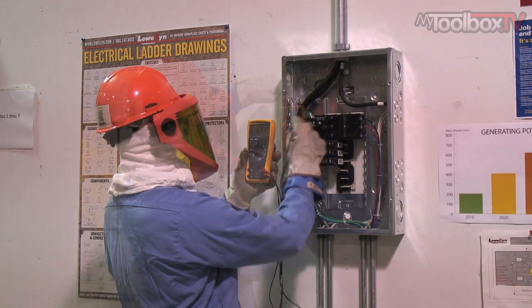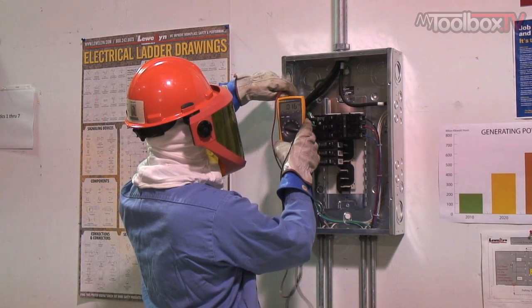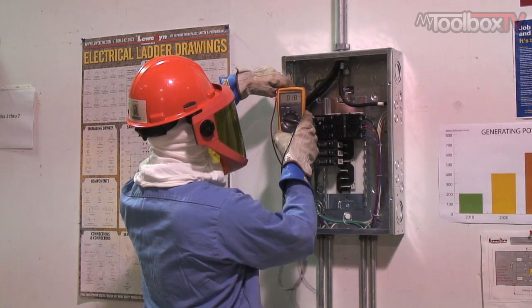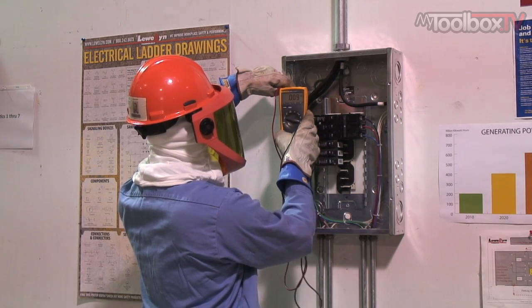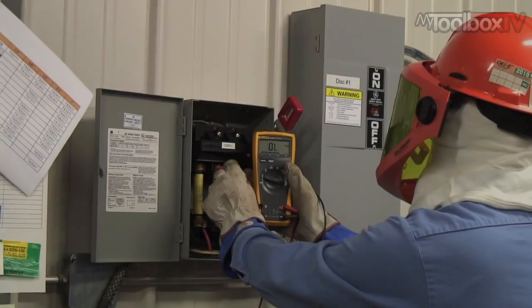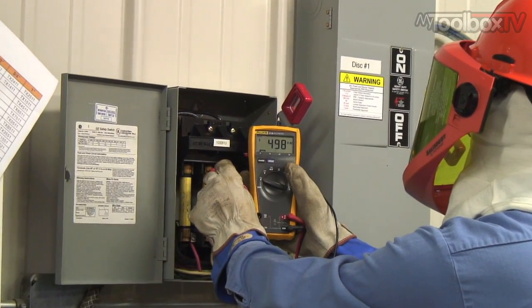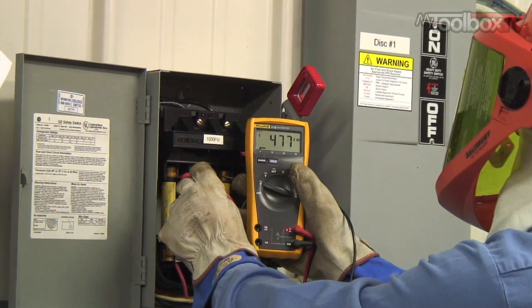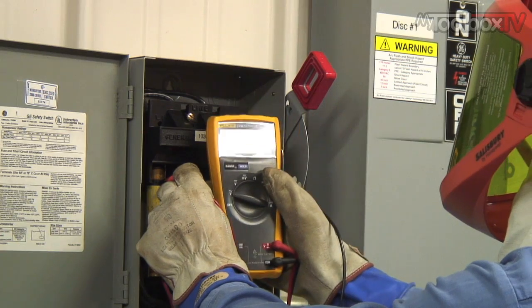He's now verifying the voltage has been removed from the main side of the circuit breaker. And you'll notice he's measured between each phase and each phase to ground. And that is a voltmeter. There's a good voltmeter that is capable of that work.